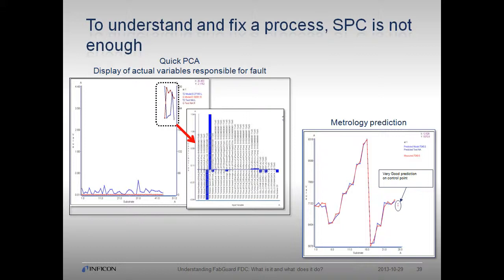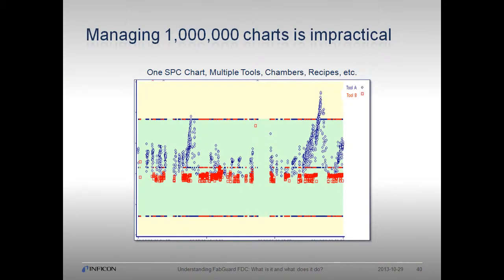Using a PCA model, we can drill down to variable contributions for out-of-control data to determine what part of the tool contributed to the fault condition. Additionally, we can create a metrology model that predicts measurement based on process data and then compare the prediction to the actual value. FabGuard also allows a report to be created for multiple tool-chamber-recipe combinations, consolidating many reports into a single report with independent execution.